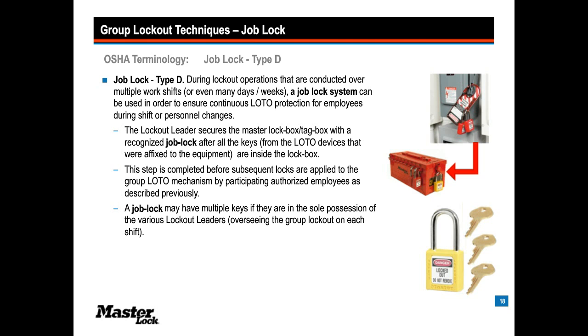But OSHA particularly does allow for a sharing of keys or multiple keys to the same lock under the circumstances that the job lock leader does not physically work on the machine unless their personal lock has also been applied to the lockbox. Okay? So I think that pretty much explained it.